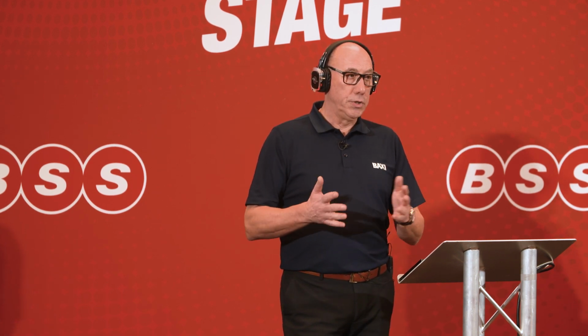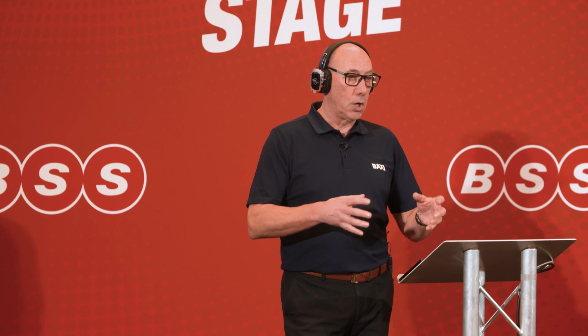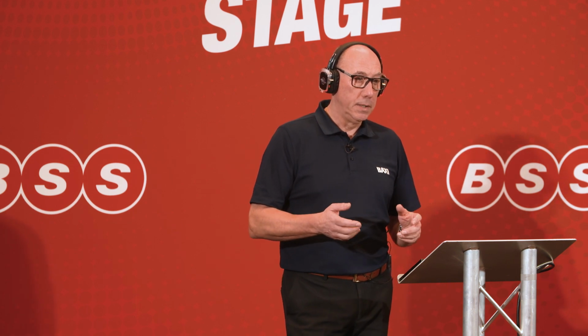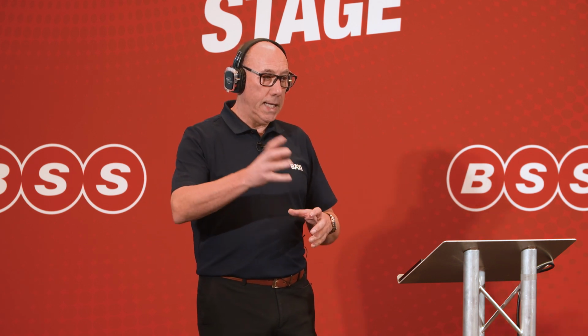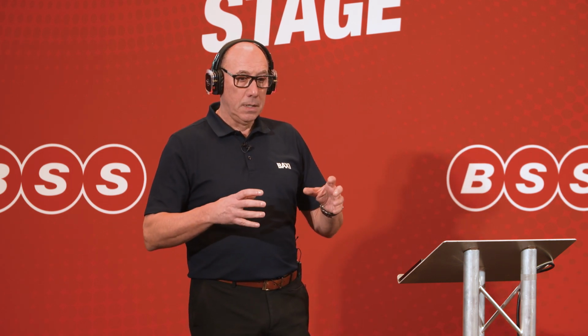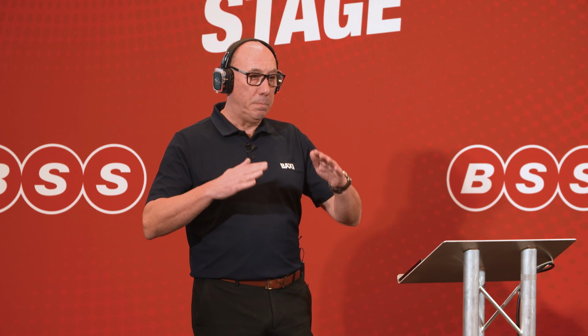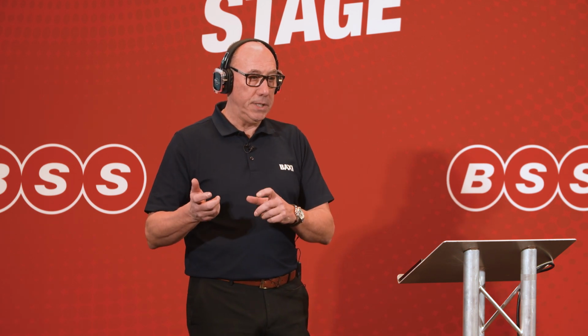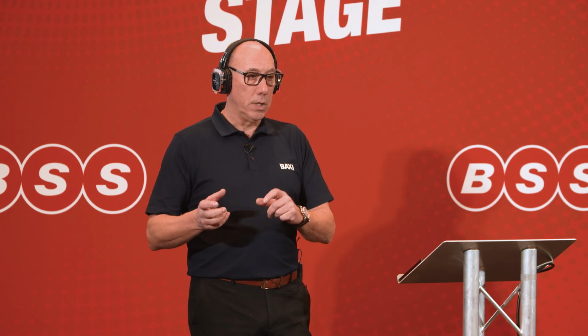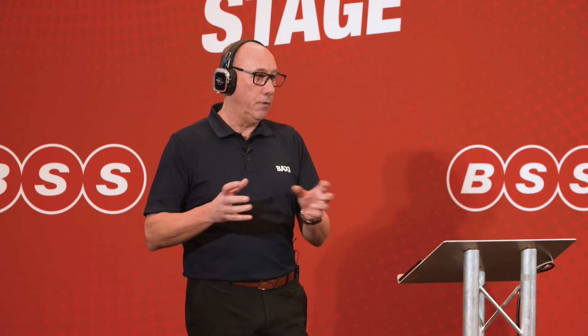The other thing we also forget is that with all these systems, complicated BMS systems are required. When you're putting in heat pumps and standard gas boilers or CHPs or whatever, the BMS has to be able to balance out the bivalent type system, because one can often cancel out the other. That's when it all goes wrong, and that becomes hellishly costly for the owners.